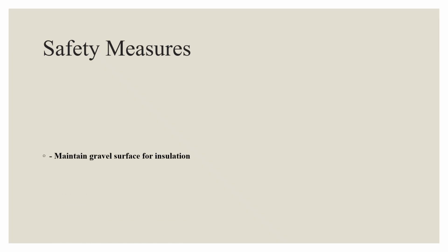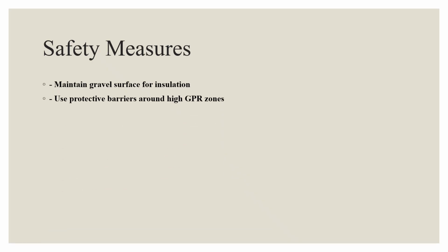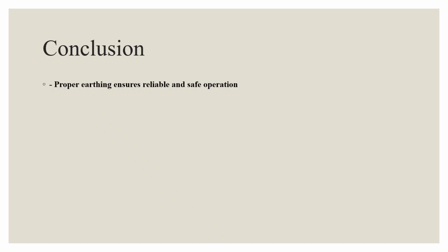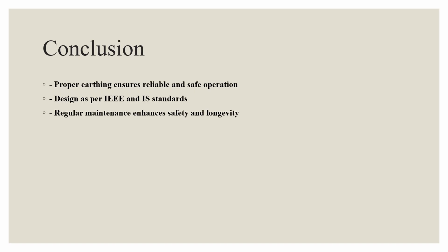After the designing, we have to take some safety measures, which include maintaining a gravel surface to increase insulation, fencing high potential areas, and labeling all grounding points clearly. This ensures operator safety under fault conditions. Now to conclude, proper earthing design ensures safety, reliability, and long-term operation of a substation. By following IEEE and IS standards, using corrosion resistant materials and maintaining the system regularly, we can protect both equipment and persons from electrical hazards. So that's why designing the earthing grid and maintaining it is crucial.